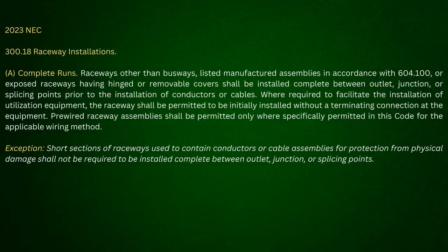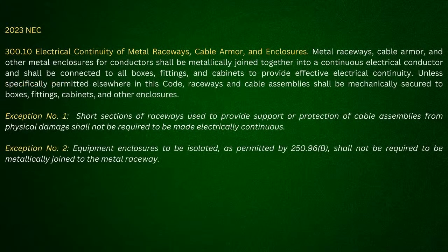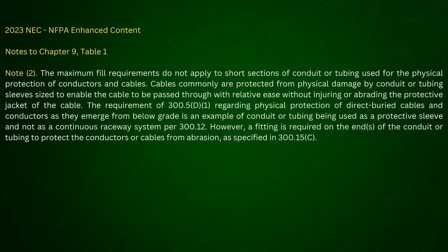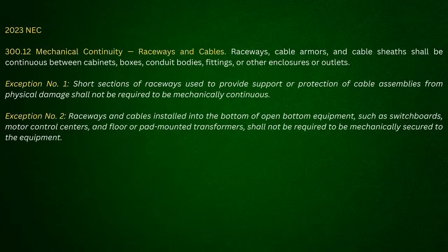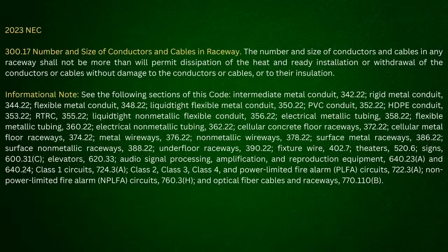Now, what does the exception say? Short sections of raceways used to contain conductors or cable assemblies for the protection of physical damage shall not be required to be installed complete between outlet, junction, and splicing points. Why is that? Because the short section, even looking back here at note 2, through the NFPA enhanced content, they tell you that it is what? A sleeve. Yep.